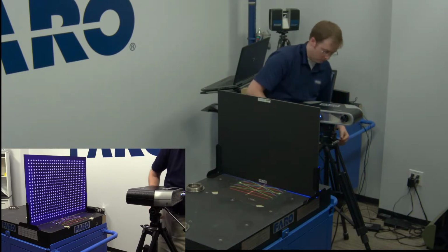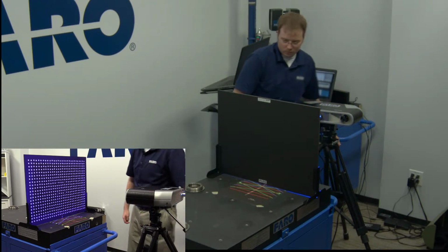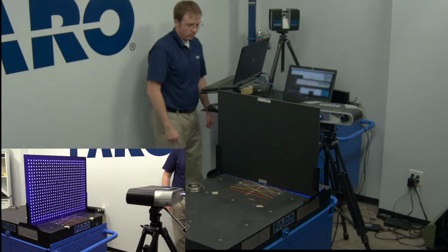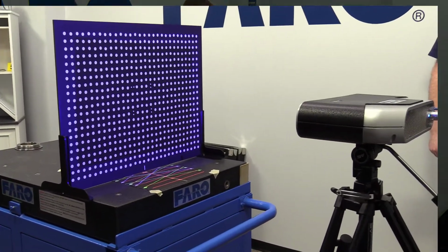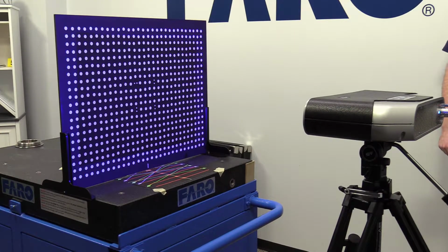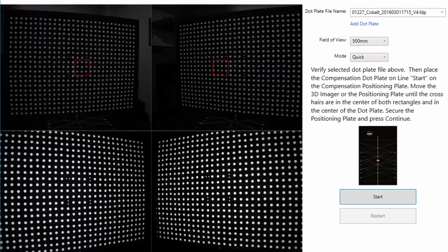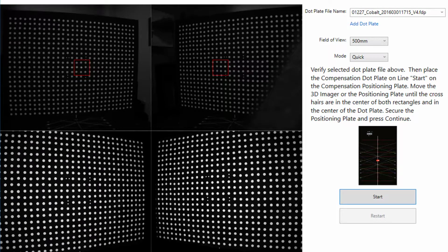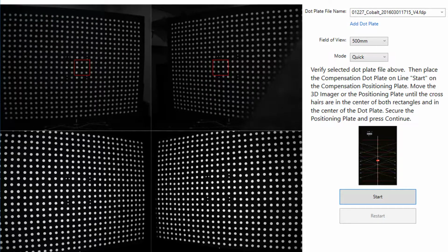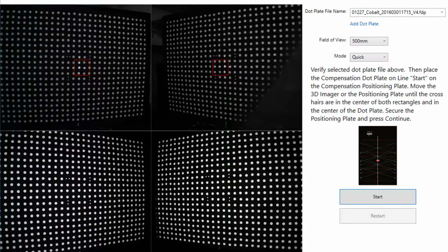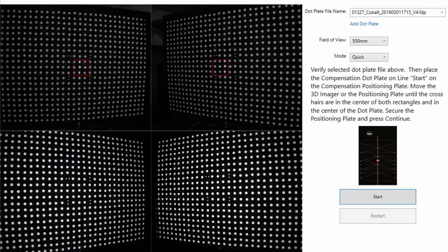You may have to move the tripod side to side and/or up and down. At the moment, this will only modify and set these two directions. This can be done by adjusting the pan and tilt on the tripod. Once the crosshairs are located in the center of the calibration dot plate, use the screen on the computer to fine-tune the distance of the Cobalt to the dot plate. The Cobalt is at the optimum calibration distance when the crosshairs are inside the red square.